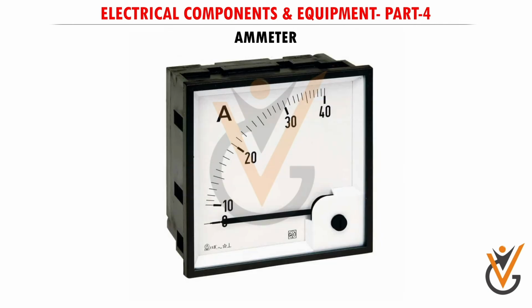Ammeter. An ammeter is an instrument used for measuring electric current flowing in an electric circuit. The rated max current drawn by particular equipment, for example a motor, is set with a red indicator needle. At any cost, the black needle should never exceed the rated max current, except at starting time. If current drawn is above the max level, it indicates there is a fault and it will lead to heating up of the motor followed by breakage.